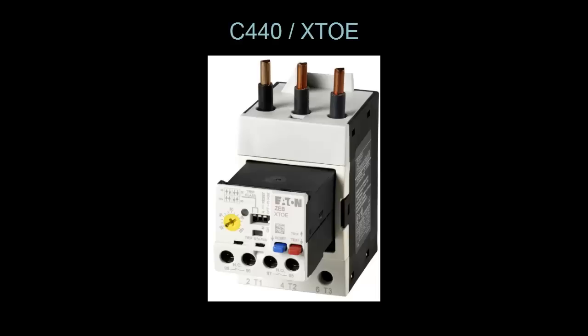This is a C440 overload relay. It has dip switches on the front that let you toggle between automatic and manual reset, as well as adjust the trip class.